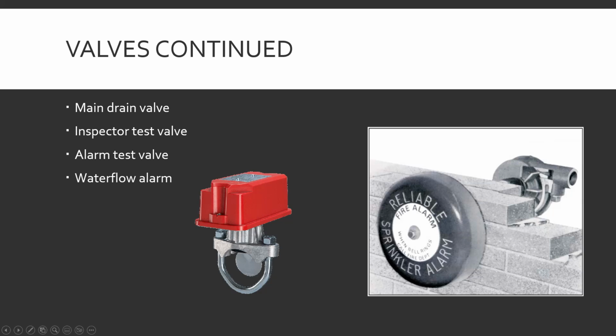So this is like you see in old movies, where the fire trucks pull up to an alarm going off, and there's a bell ringing outside the building. They have to go in, and water's going somewhere. There could be a cracked pipe, a frozen pipe that burst, someone hit a sprinkler head with the forklift, or a real fire. Don't know. This is just saying, hey, there's water flowing in the system. Figure out what's wrong.